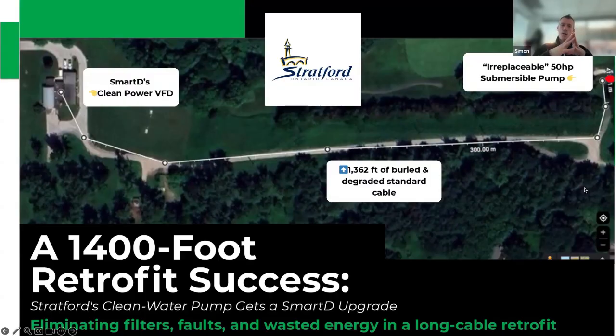And this is a use case where they actually tried to put a standard VFD first, and it failed. Despite putting a VFD and putting filters, they had to pull it out. It was faulting nonstop. On the contrary, they put the clean power VFD, no filters needed, directly connected to the drive. You get pure sine waves, go over those 1,400 feet, no problems. And again, you've got a recipe for very quick ROI on a retrofit. You go from a contactor to a VFD, and you don't have to go through the hassle of mitigation and of what could potentially go wrong here.